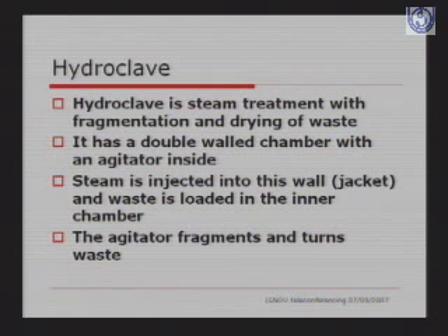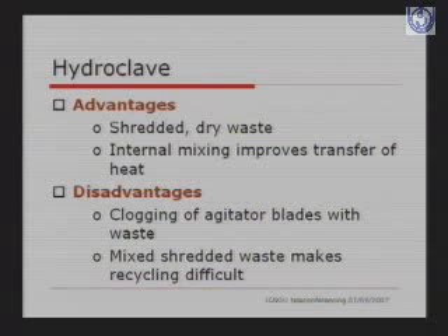The agitator fragments and turns the waste into smaller particles. It's like a mixie, yes. The other advantage with all the hydroclaves and the autoclaves, as I said earlier, is the microbial disinfection level. That's very, very high, 7 log 10. And the advantage with the hydroclave, which is not there with the autoclave, is we get a dry waste. There we have waste which has some moisture in it, and it's easily shredded here.